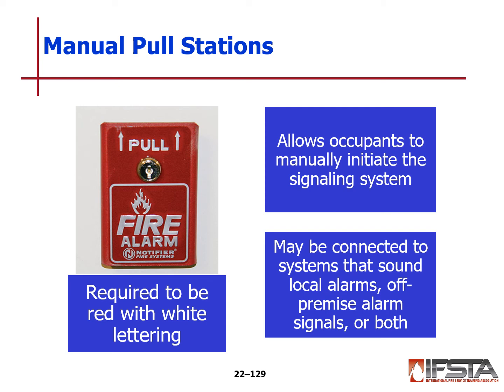Most familiar to us are manual pull stations. These are required to be red with white lettering. They're required to be mounted at a certain height and visible and not blocked. This allows occupants to manually initiate the signaling system. They may be connected to systems that sound local alarms, off-premise alarm signals as well, or both.